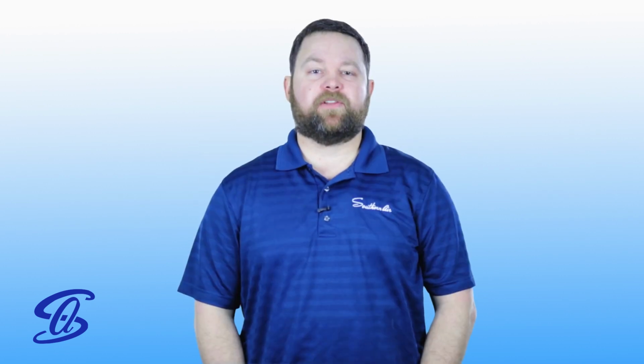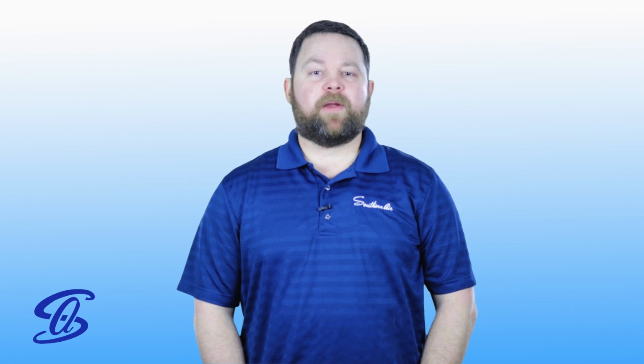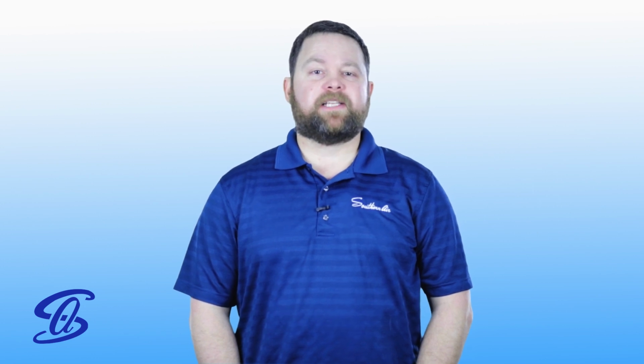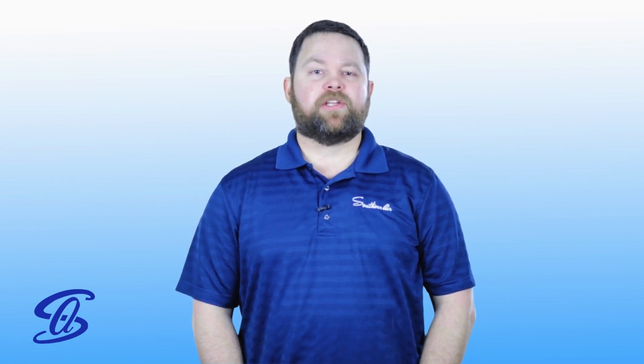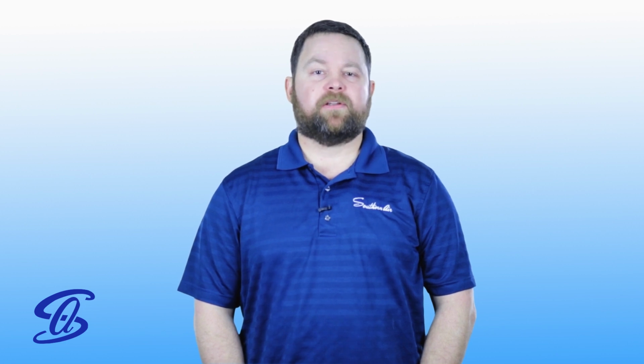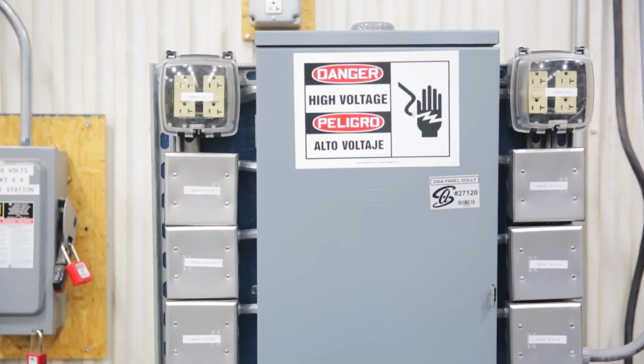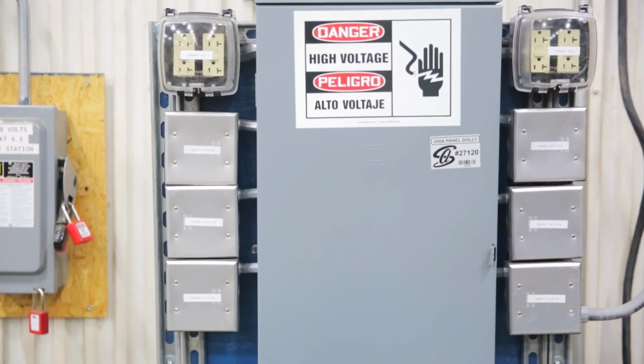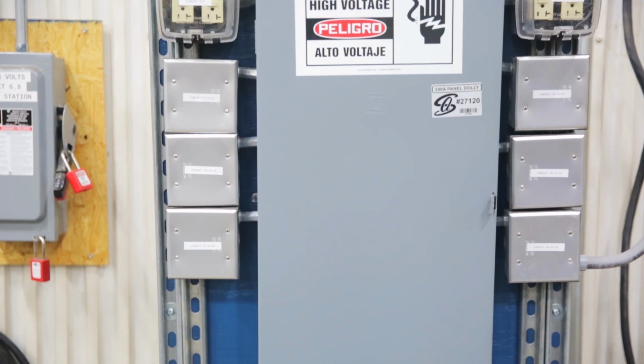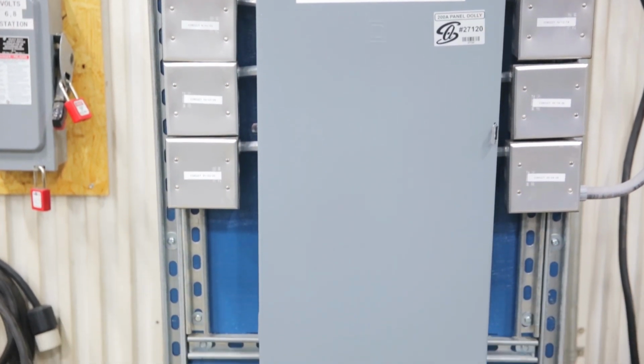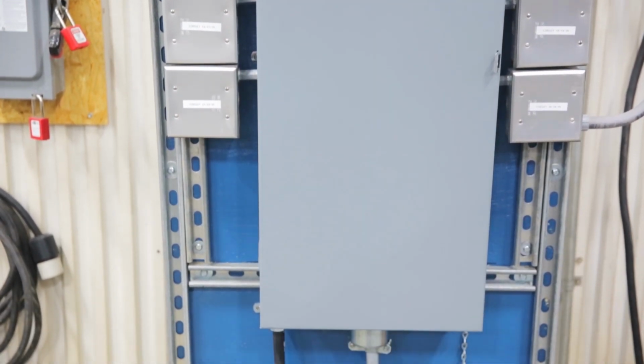Temporary power panels provide safe, reliable interim power for construction sites by bringing power from overhead or underground electrical utilities. A temporary power panel for a construction site typically consists of a meter socket, circuit breakers, and receptacles wired together in a weatherproof housing. They should always be secured on a wall or pedestal. At Southern Air, our electricians have developed easy-to-use temporary power panels. While some can still be found attached to plywood frames, this is not ideal.